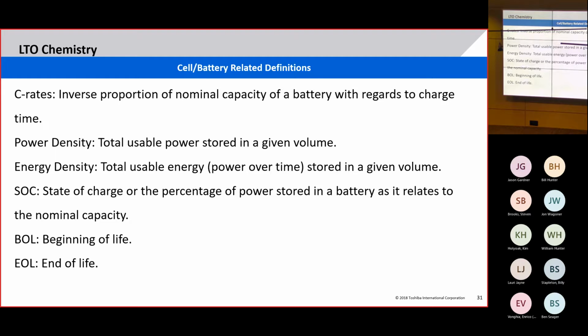It does self-discharge, but it's a lot slower than VRLA because, as we discussed, the internal impedance is very low, so the self-discharging is also very low. Typically you're going to get a year plus before you have to recharge those batteries, depending on the sensitivity and the threshold you have for dipping it, how low you can go. If you can go down to 0.5 or 0.7 volts, it might be a little sooner than one year, but it can last up to a year on the shelf, basically.